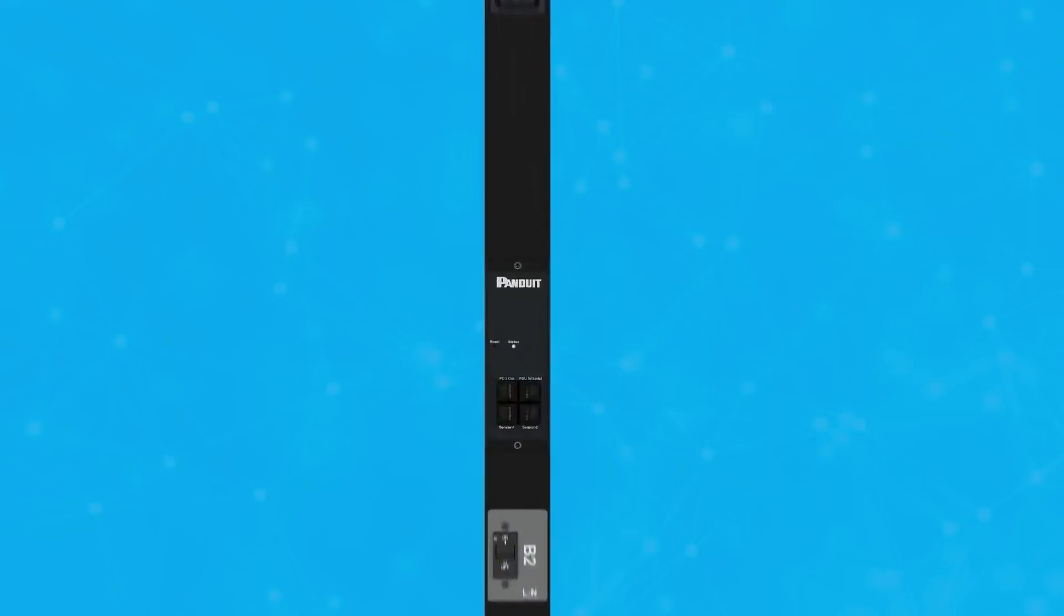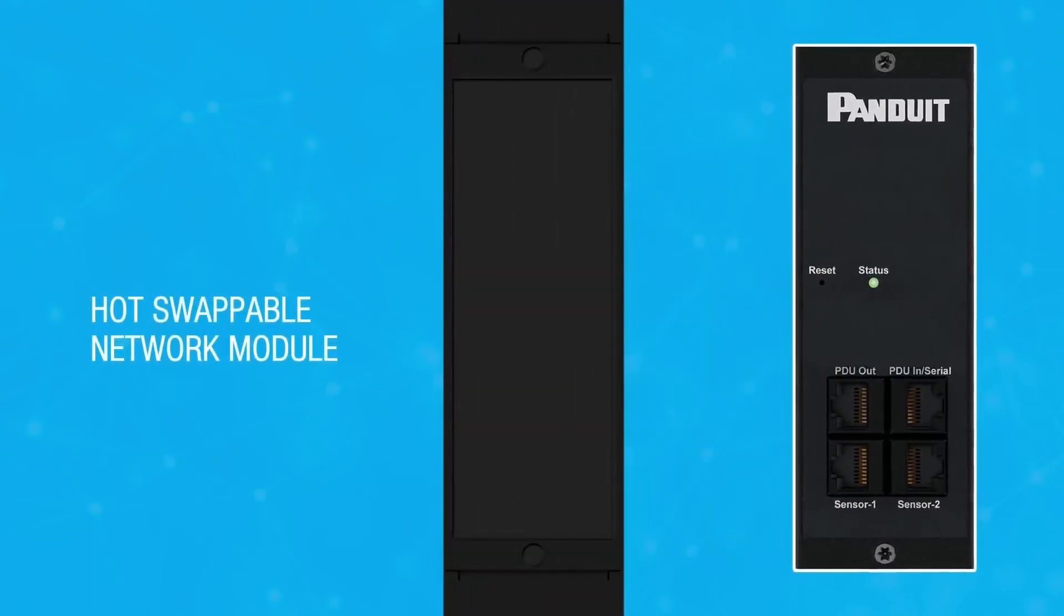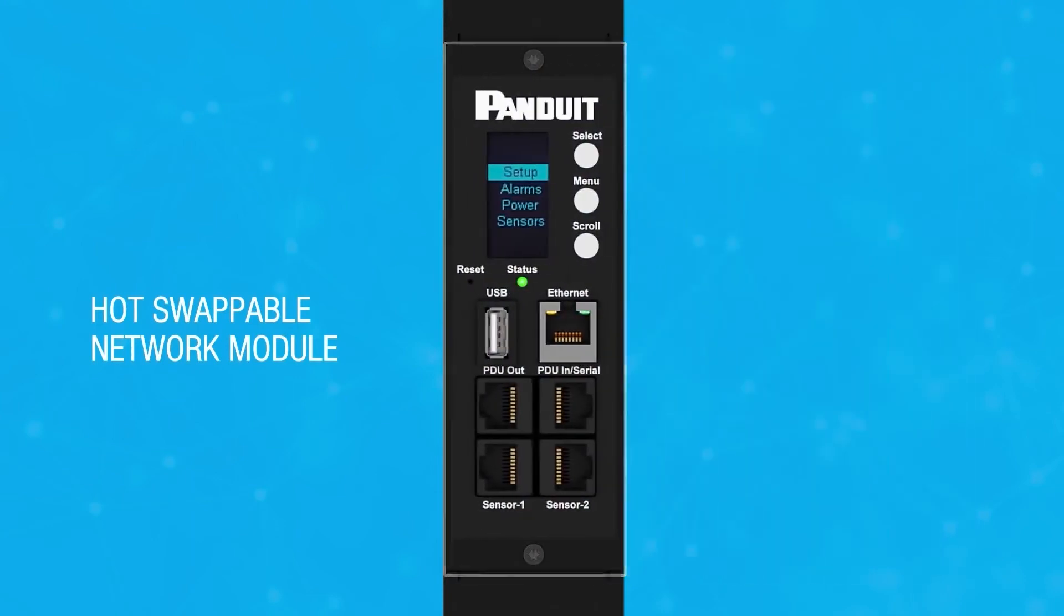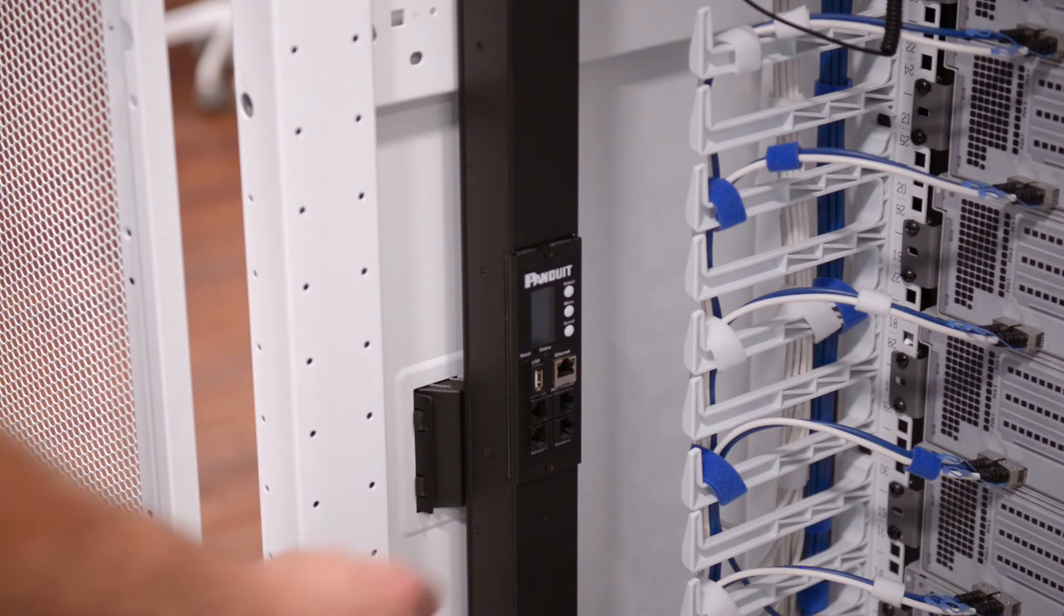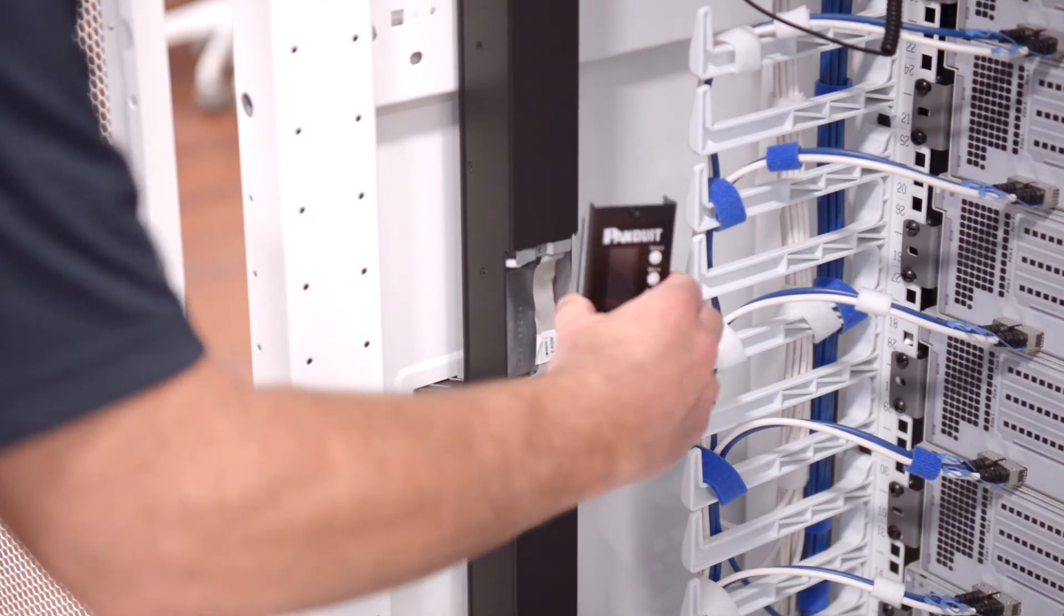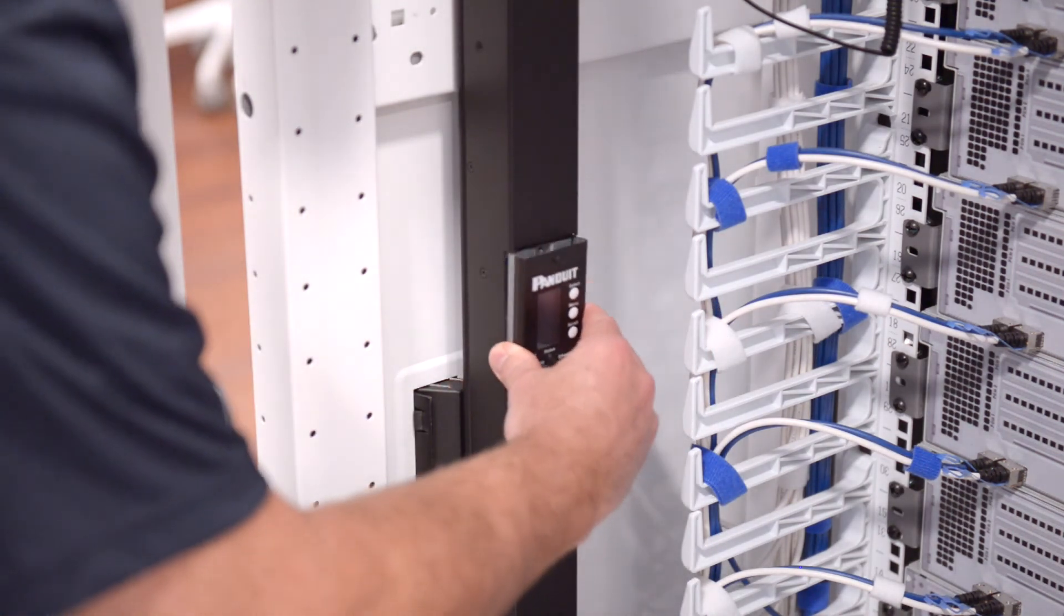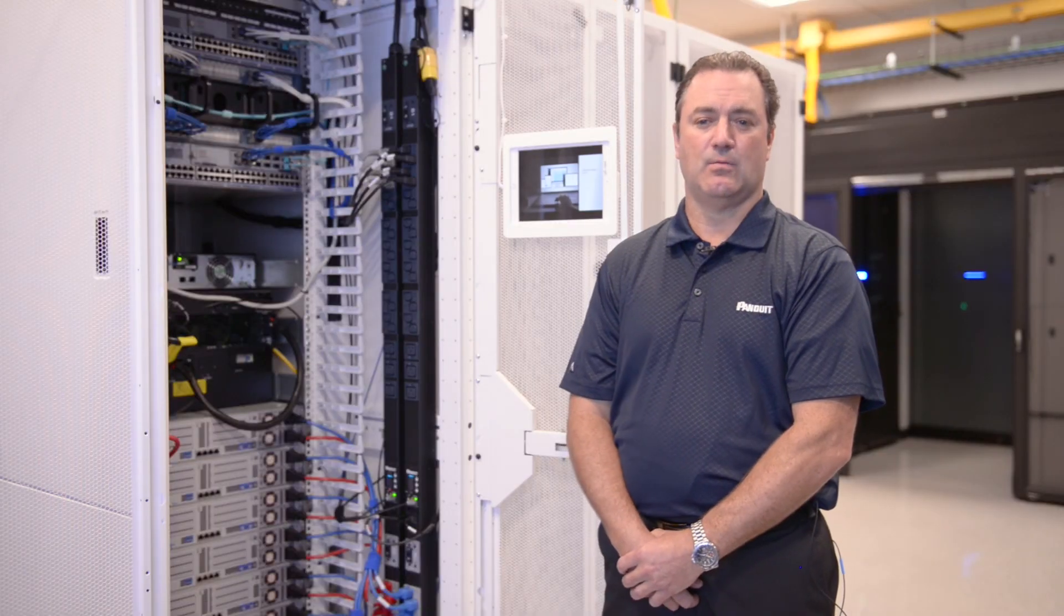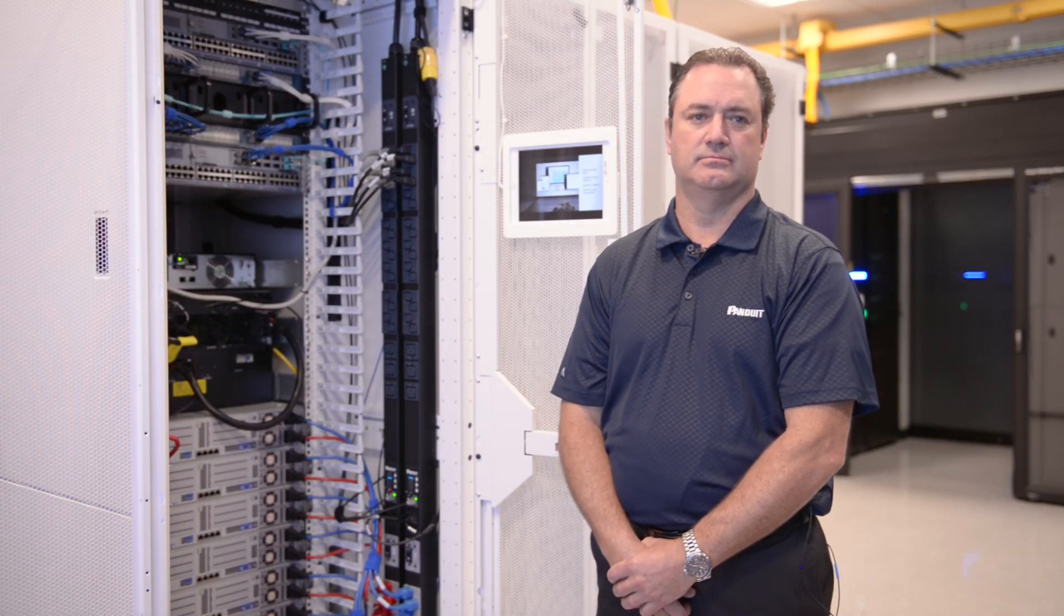Lastly, what's really impressive in addition to the value the controller provides is that the controller itself is hot-swappable, which means you can replace, remove, or reorient it as needed, and you never lose power to the PDU, which means your critical IT assets never lose power. This helps you mitigate risk and save time. Thanks for watching. I hope you've learned a bit more about the value and importance of the PDU controller.